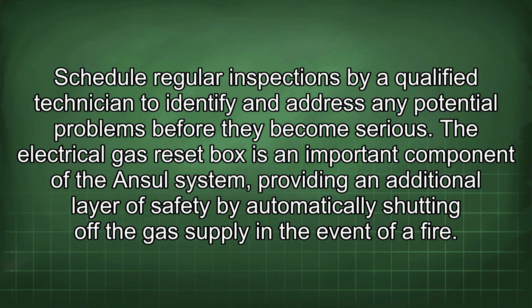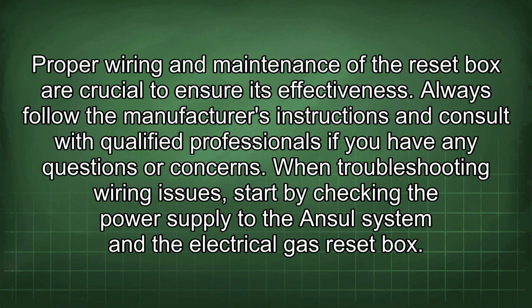The electrical gas reset box is an important component of the Ansul system, providing an additional layer of safety by automatically shutting off the gas supply in the event of a fire. Proper wiring and maintenance of the reset box are crucial to ensure its effectiveness. Always follow the manufacturer's instructions and consult with qualified professionals if you have any questions or concerns.